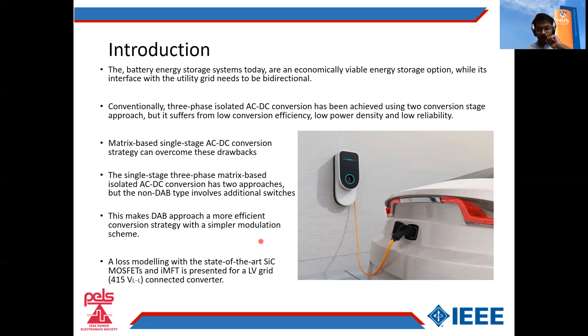So coming to the topology, you can see that there is a 3 cross 1 matrix converter at the front end and a conventional H bridge at the back end. The switches S1 to S6 are 4 quadrant switches which convert the three-phase AC to medium frequency AC. So the isolation MFT in the middle has this leakage inductor integrated into it for a better power density and provides medium frequency isolation and also the required voltage step down.